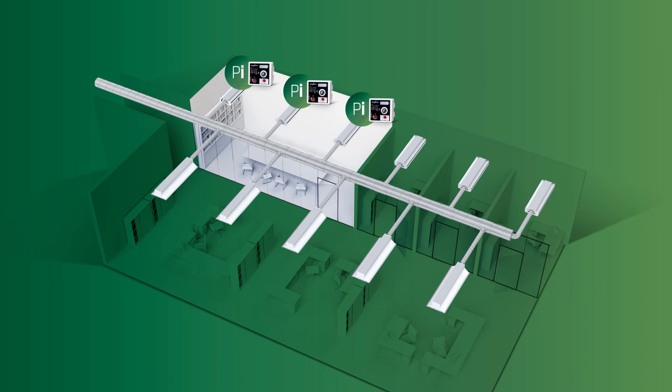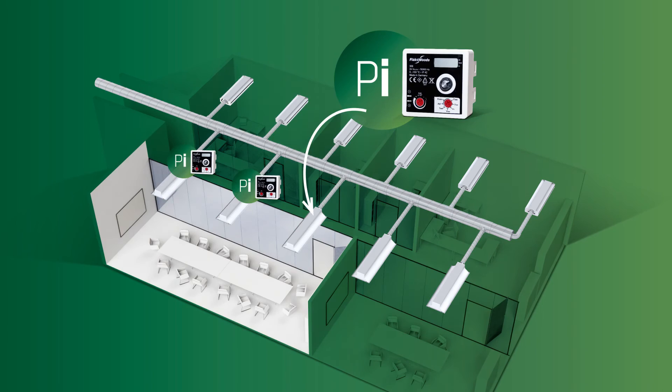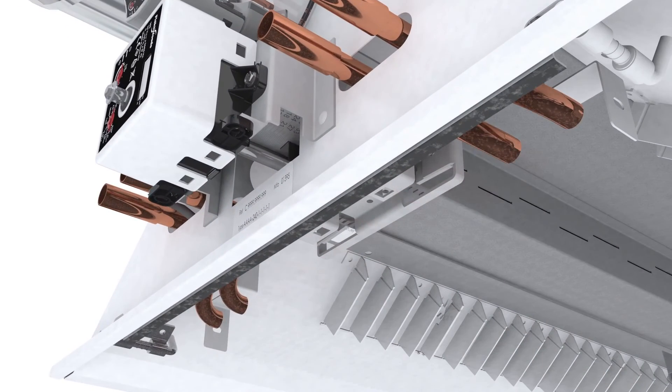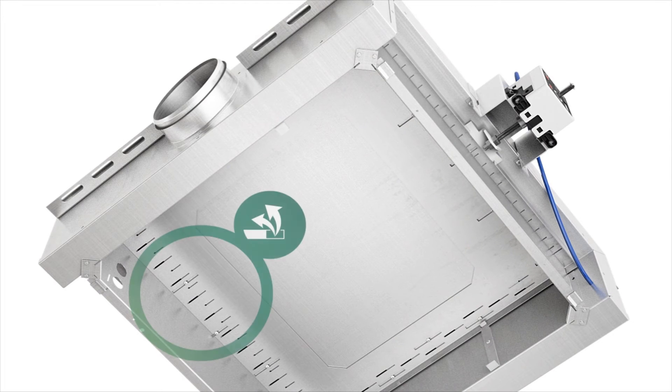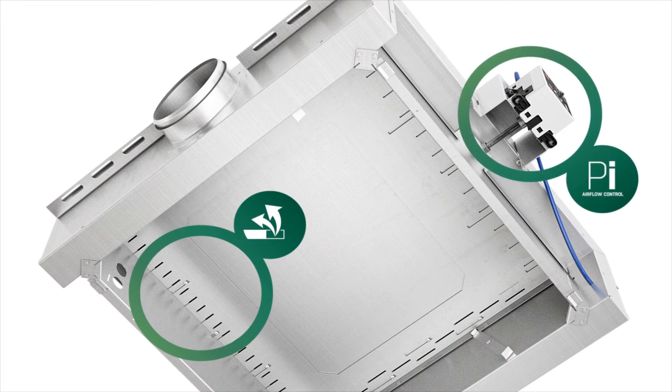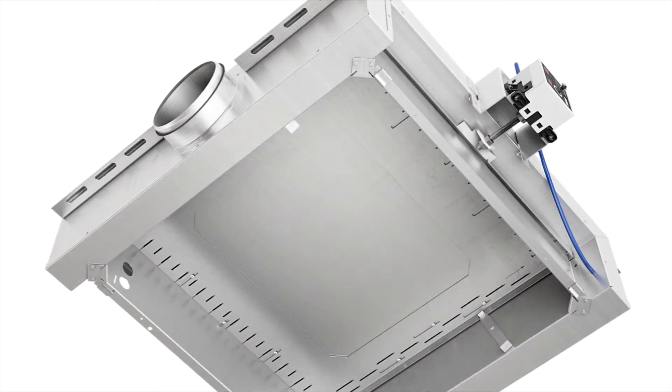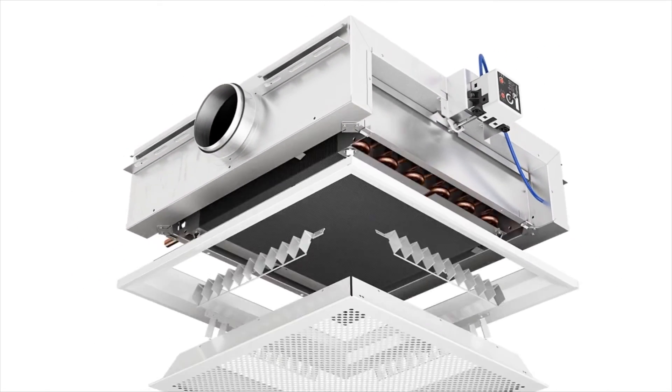The PI actuators can also be moved between rooms to adapt to redesigned floor plans. The new PI function actuates the nozzles, which will compensate for any local pressure fluctuation and restore the airflow. It also reduces the need for balancing dampers — and less dampers means lower system pressure, which in turn means energy saving.